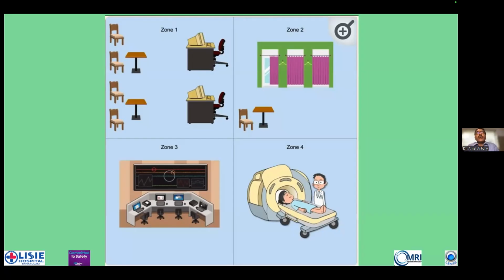In this restricted area, only the patient and authorized persons are allowed to enter, and persons entering this area should be screened before they are allowed to enter. Zone 4 is the MR equipment room, and here only the technician is allowed to enter, and under the supervision of the technician, the patient is allowed to enter. There has to be complete screening before anybody enters Zone 4, and any other medical personnel who comes in support of this patient should also be screened completely, and under the supervision of the technician should be allowed to enter. And remember, the door to this room should always be closed, except when the patient is allowed to enter, and even when the patient is being positioned, it's ideal that the door is kept closed.